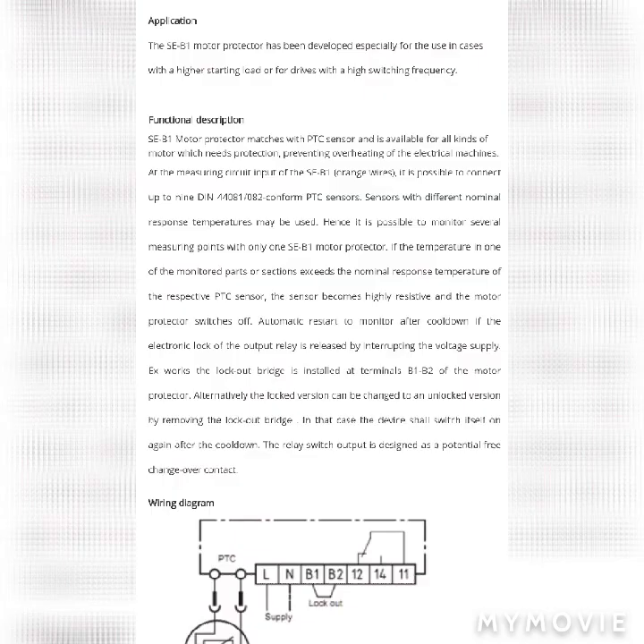The motor protector SE-B1 type is a motor protector that senses your motor's coil winding temperature. When it senses that the temperature has exceeded the equivalent PTC resistance connected on your motor, the motor is automatically shut off.